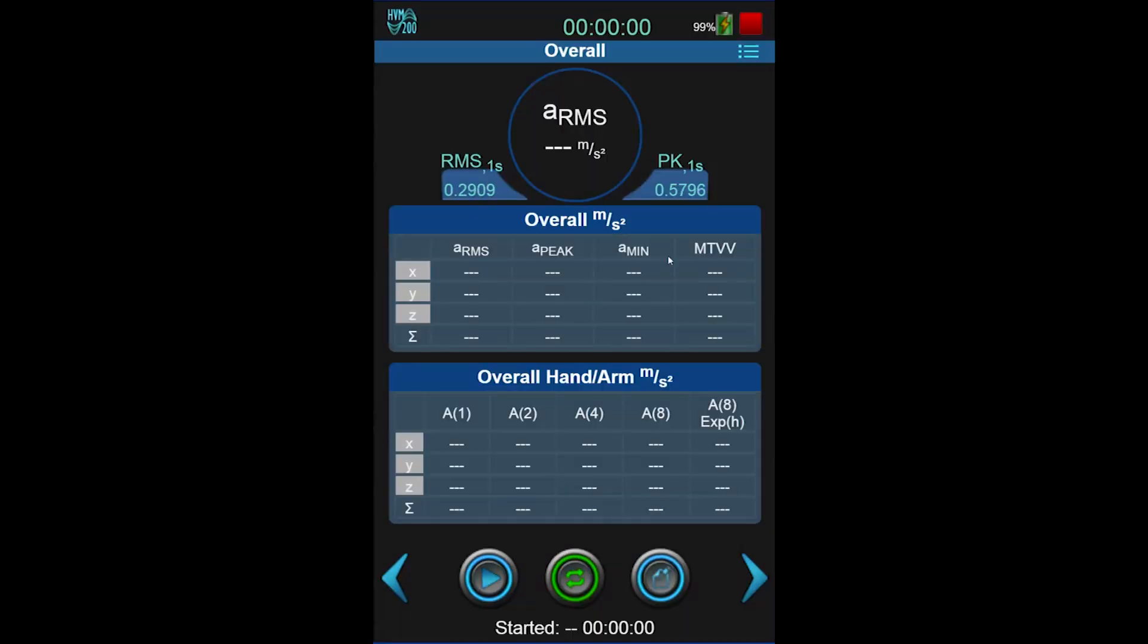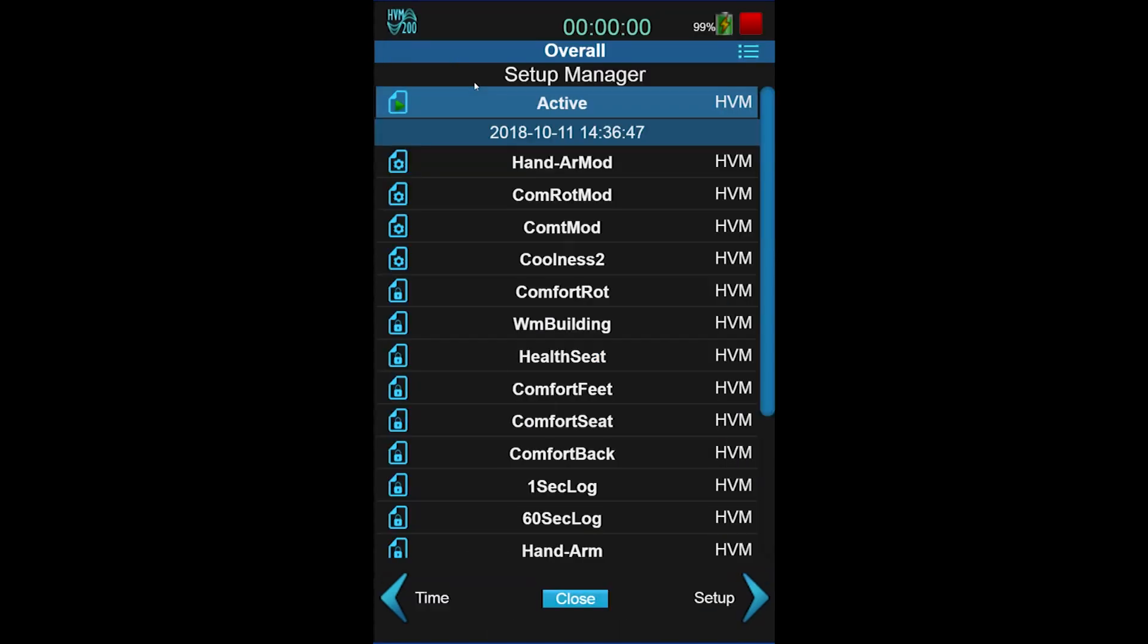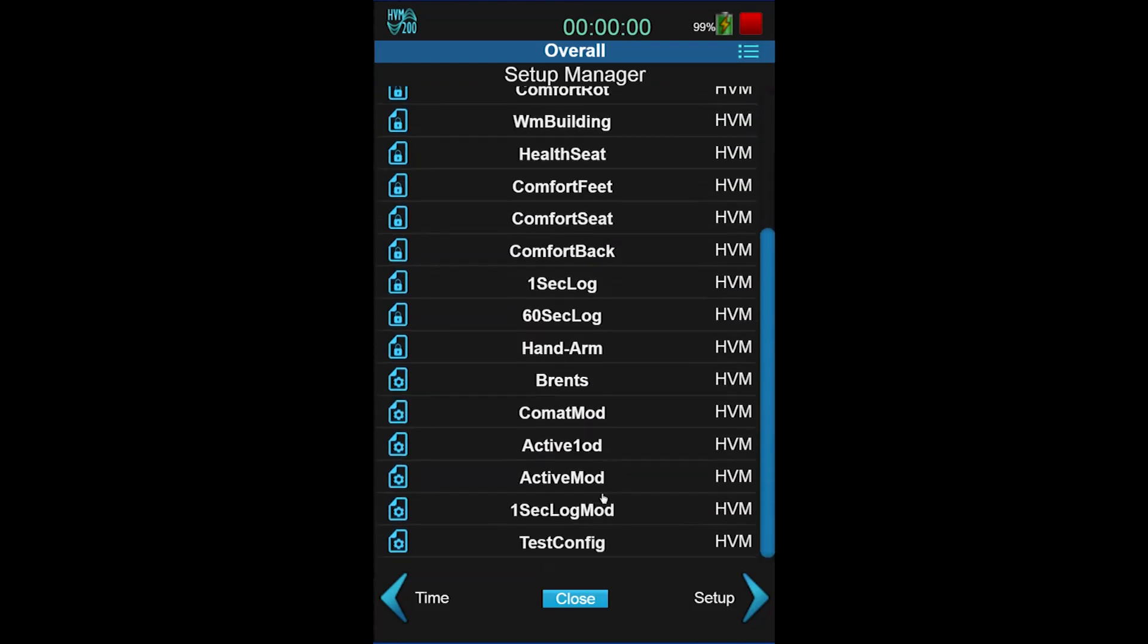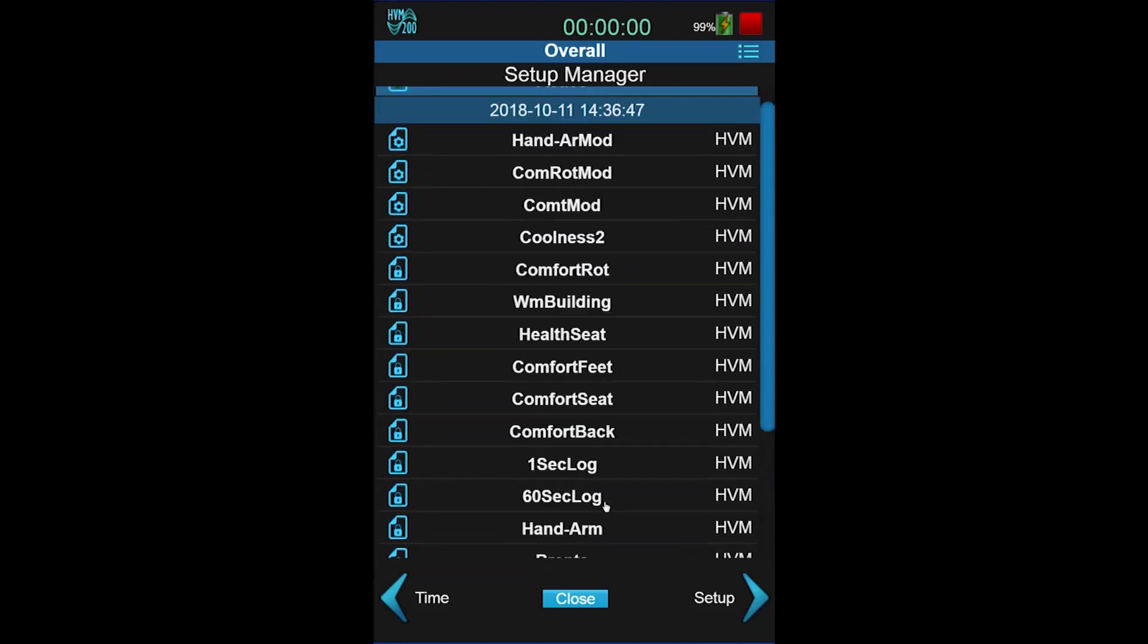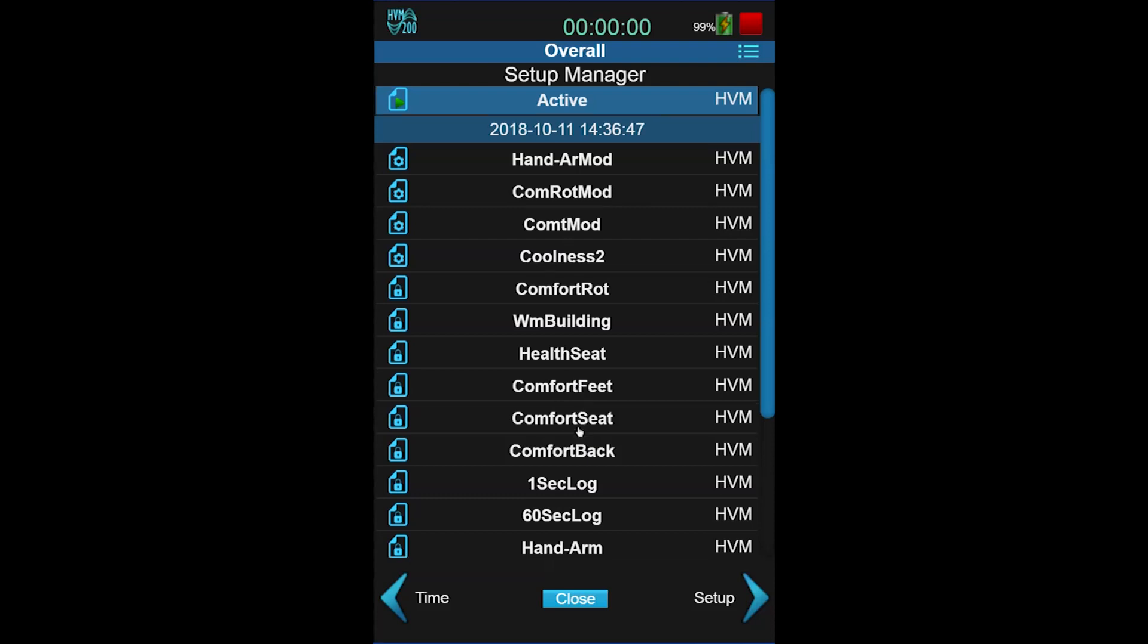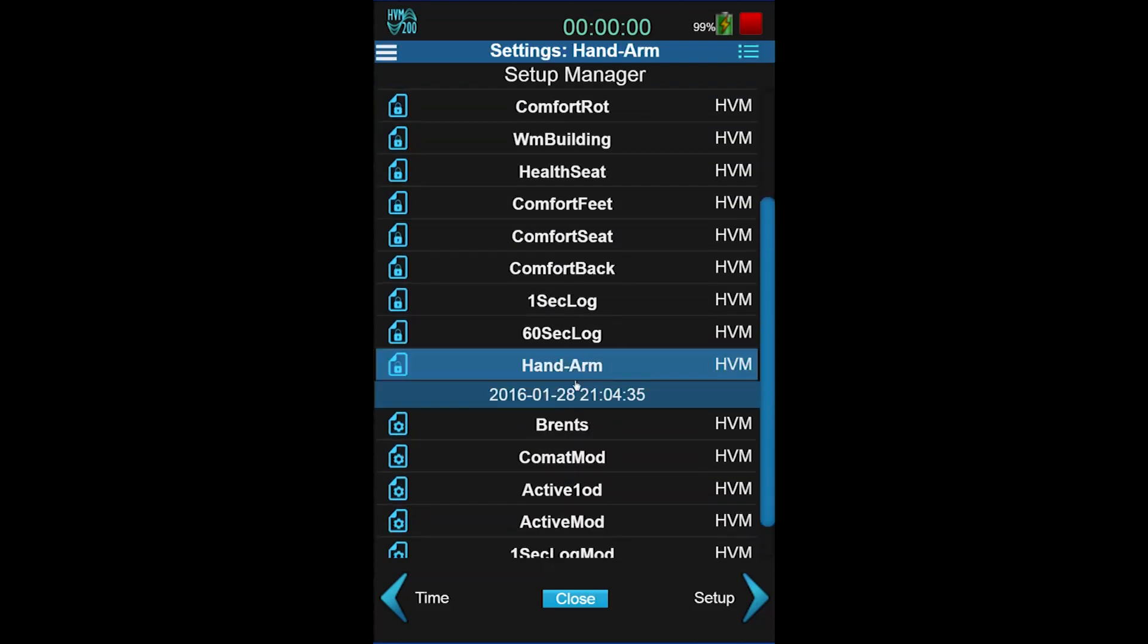To set up the measurement, go to the Tools menu, then select Settings. You can see a hefty list of default vibration settings. We want the default setting for Hand Arm. So press and hold Hand Arm until the menu pops up, or if you're on G4, double click. Select Set to Active.